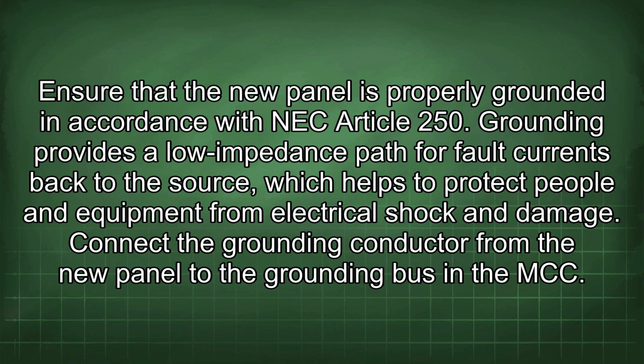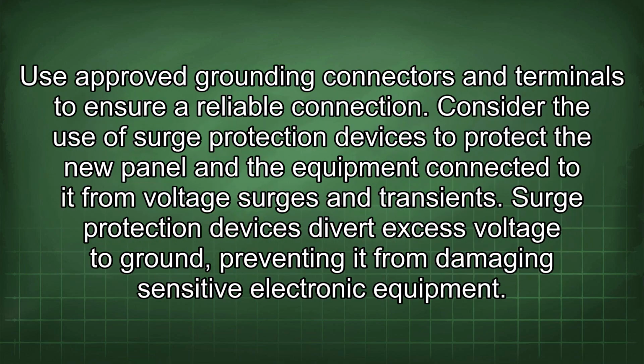Ensure that the new panel is properly grounded in accordance with NEC Article 250. Grounding provides a low impedance path for fault currents back to the source, which helps to protect people and equipment from electrical shock and damage. Connect the grounding conductor from the new panel to the grounding bus in the MCC. Use approved grounding connectors and terminals to ensure a reliable connection.